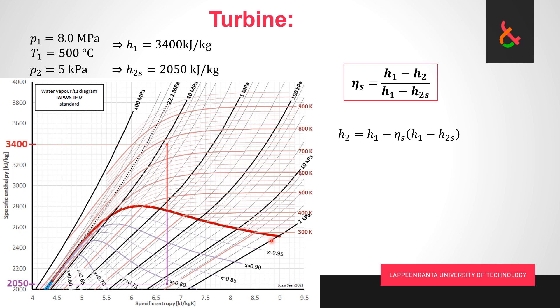That is our h_2s, and now we have all the variable values for this equation. We plug in the numbers, see what comes out: h_2 = 3400 - 0.85(3400 - 2050) = 2250 kilojoules per kilogram. As simple as that, and now we know the state of the steam exiting the turbine.